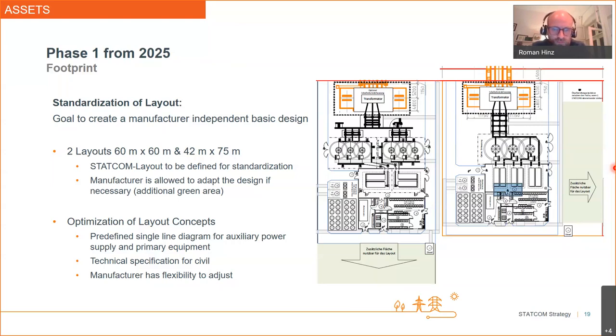And for us, it was a goal that the STATCOMs we tender have more or less the same topology. For example, when you go into the control building. For us, the goal was that when you order one supply, you do not get a converter building which is different from the next supplier's. And this was for us really important. So that's the reason why we created several civil designs for our buildings. And we also checked with the manufacturers that they can fit their design. And so in our current tender, we are forcing the manufacturers to apply to our building design. And that's the reason why we also made a specific civil specification.